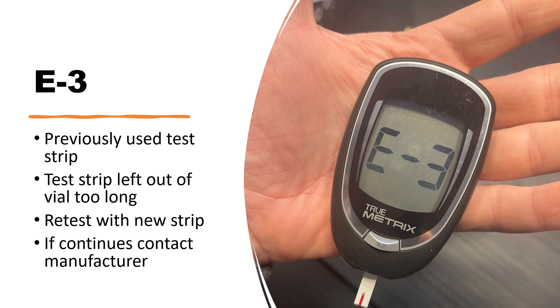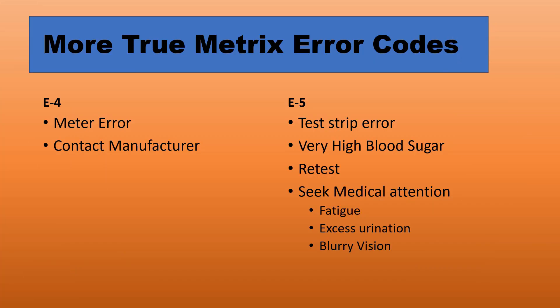Simply retest with the correct test strips and that should take care of E2. E3 indicates that you're attempting to reuse a test strip that has been previously used, or that the test strip was left out of the vial too long. Simply use a new test strip and retest. If it continues, you can contact the manufacturer.